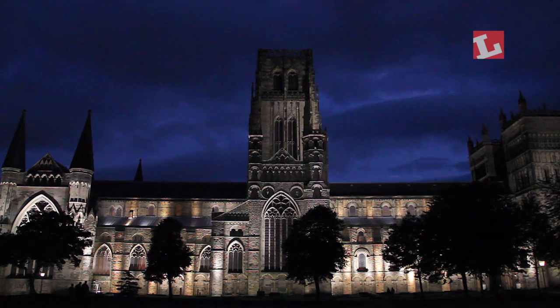My name is Anthony Smith, I'm a director at Stainlight Design Services, and I was lead designer on the Durham World Heritage Site project. We were given a target of 33% energy savings over the entire site. We've achieved virtually 78% through a mix of reducing overall consumption, some switching, and balancing of the fittings to reduce energy where we can, so we're not over-lighting areas that didn't need it.